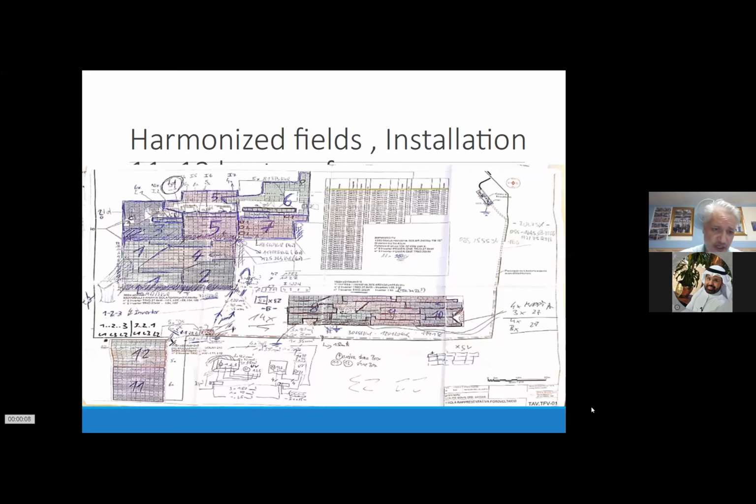In this system, you can see it's quite crowded. They changed a lot of inverters and brought different arrays into other inverters. For example, inverter number 1, which you can see is almost like a C, goes into number 4 and also hits number 2, because they're all on the same rails. So the best system was, of course, 11 and 12. That was basically the normal setup you would do.